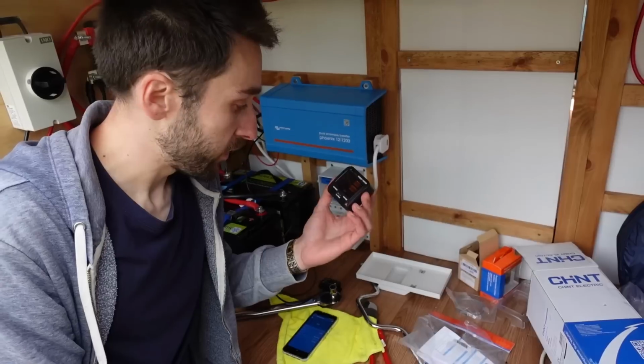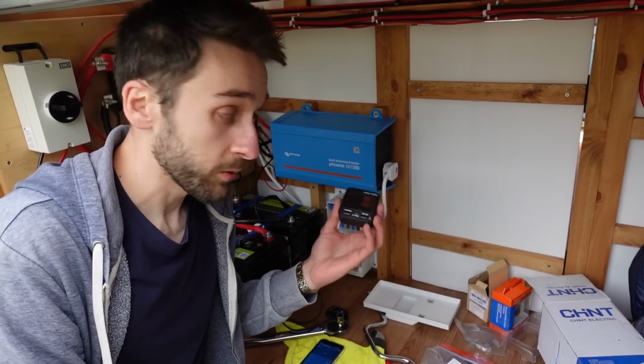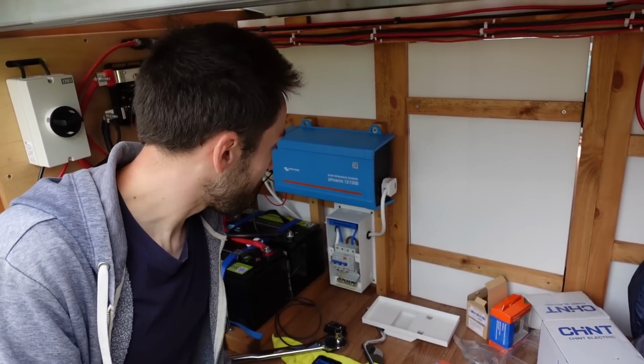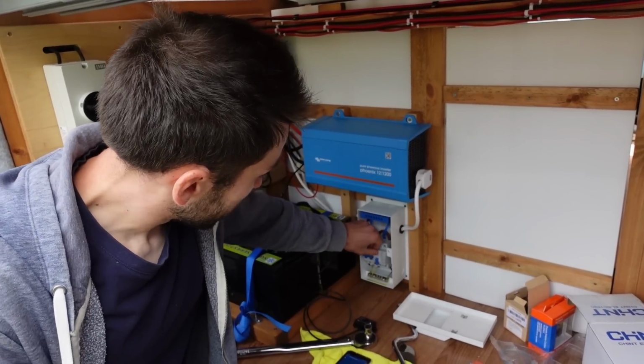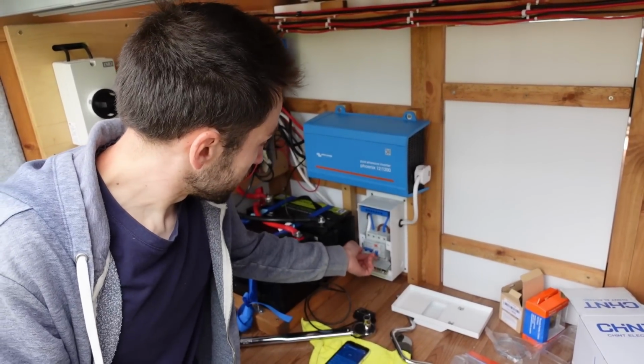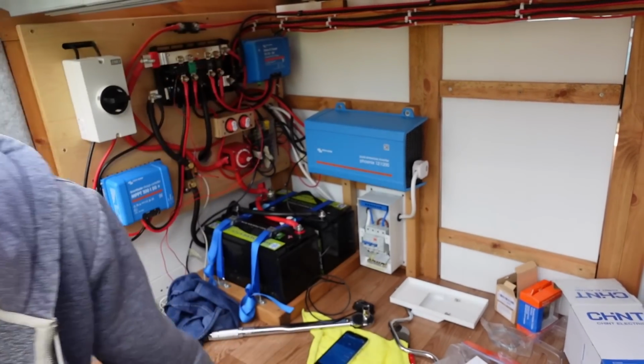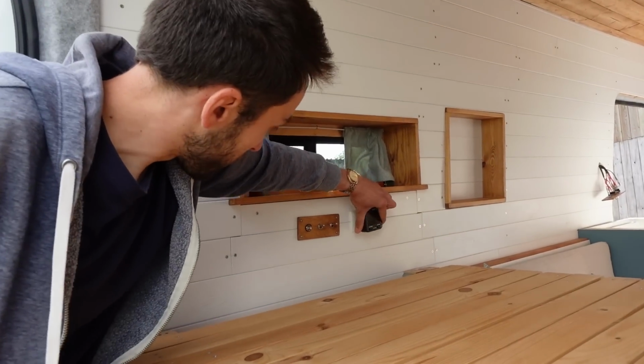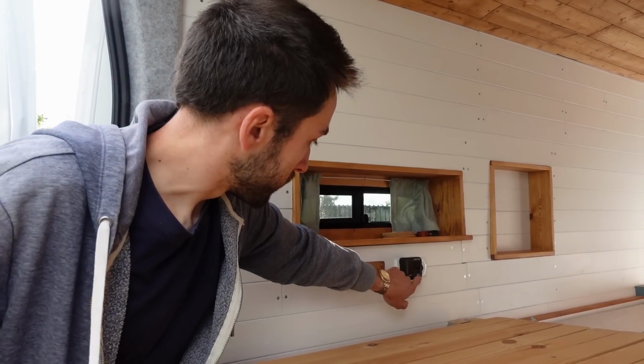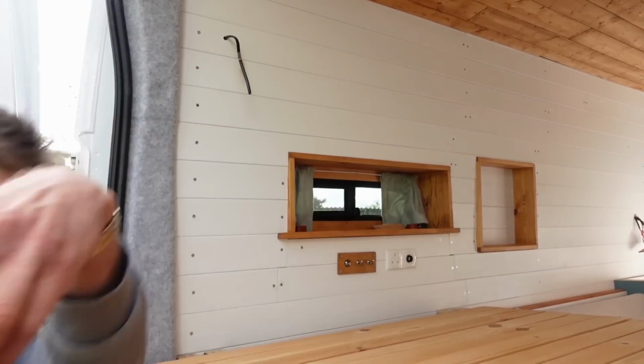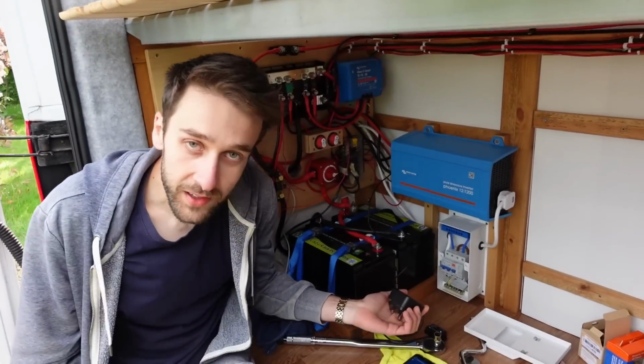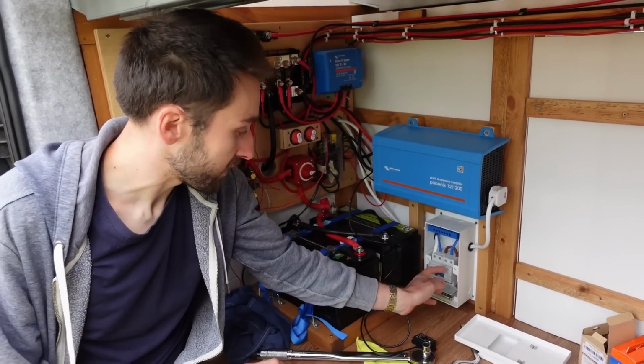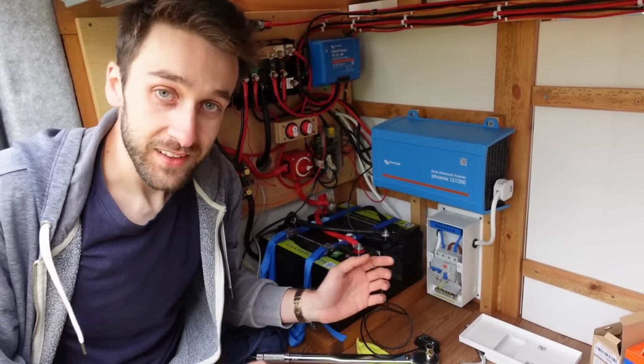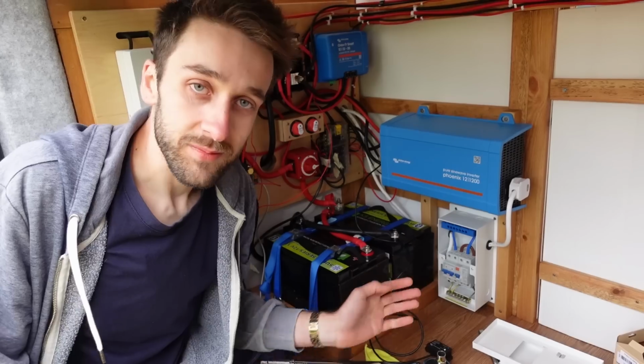So basically it's telling us that the system is not completely correct. If you plug this into a socket in the house, then you want it to say correct, and obviously that's what we want too in the van. So it is interesting because you do that and it works fine, but there's obviously an earth problem there. Now what we can do is press the RCD test button, and nothing's happening, it's not tripping. Right. So that means, as it's wired at the moment, it wouldn't actually trip if there was an earth fault. So the RCD in this configuration, even though it's doing that, is completely useless, and it wouldn't actually help us at all.